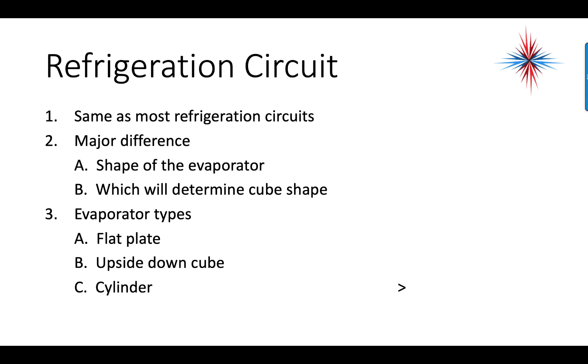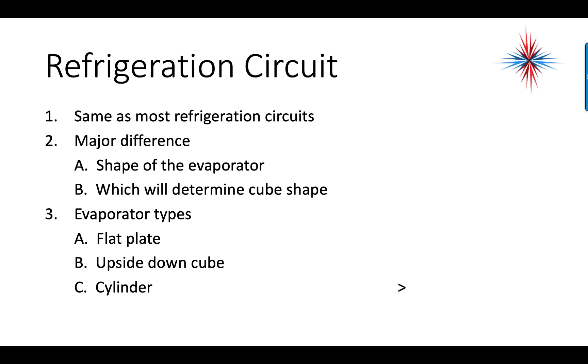The refrigeration circuit in ice machines is the same as most refrigeration circuits. The major difference is the shape of the evaporator, which determines cube shape. The evaporator types could be flat plate, upside-down cube, or cylinder. It uses a standard low-temperature condensing unit. The metering device could be TXV, cap tube, or AEV. Refrigerant in the years past, and you may still come across ice machines that use them, is R12 and 502. But today, most often, you're starting to see many other types of refrigerant. One I'm seeing very frequently is 134A.